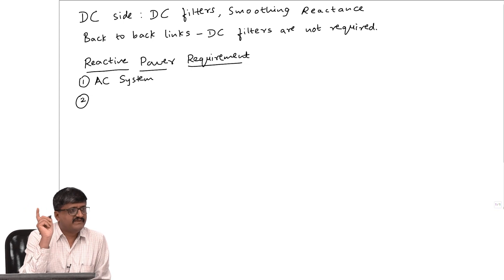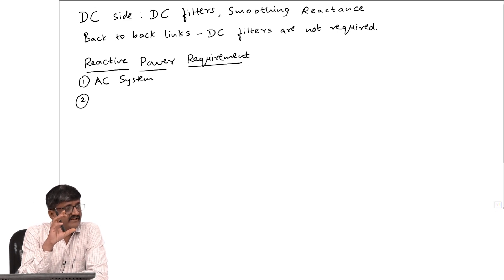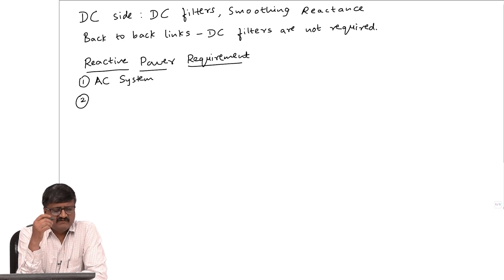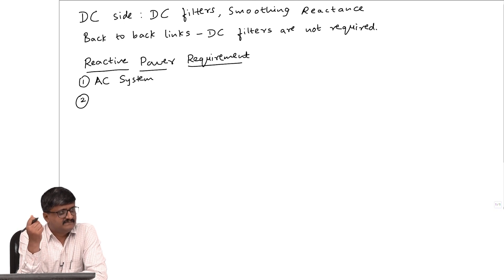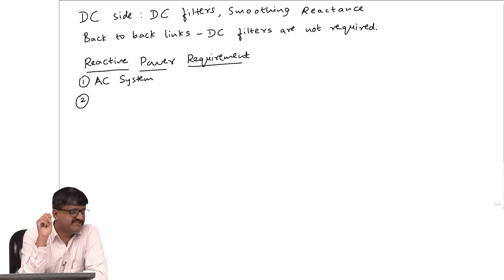Invariably there are filters on the AC side to minimize the current harmonics. These filters can provide reactive power at the fundamental frequency. When we decided the rating of the capacitor or inductor, we took the fundamental current and the harmonic current. That fundamental current is essentially supplying reactive power. The inductor and capacitor act in opposite ways: by convention, the inductor absorbs reactive power and the capacitor generates reactive power.